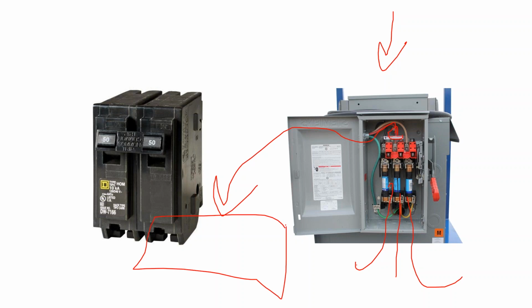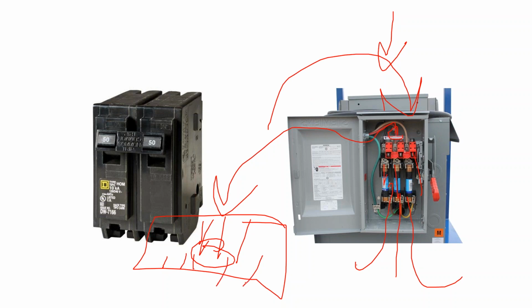Or maybe you're doing the combining at the inverter itself, but there's no room to fuse the circuits on the inverter, and so you go up to the rooftop and fuse the circuits at the rooftop, even though you're not combining. And why you might want to do that is maybe your inverter can track multiple circuits, and so you don't want to combine them together up on the roof. You want to keep them separate, but you still have to meet rapid shutdown requirements and these fuse requirements. So there's room on the rooftop for a fuse box, where you're taking all the circuits into the fuse box, fusing them, and then letting the system operate.